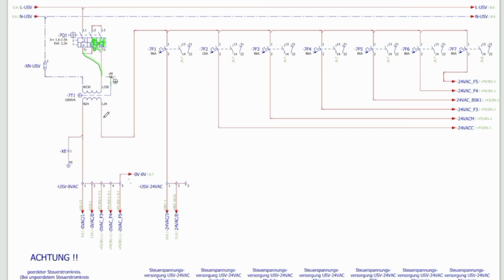One thing a bit suspicious here are the protection numbers on the transformer protection. Let's see it from the output side, the low voltage side. We can't say output or input because you can rotate the transformer. So in this case, from the low voltage side, let's do some calculations.